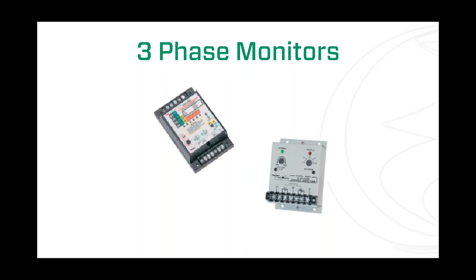So again, we start talking about 3-phase pumps, we start talking about expensive pumps typically, I would highly recommend considering one of these devices. Otherwise, you might find yourself being blamed for a burned up pump, and nobody might have even known that they'd lost a phase. But if you had one of these guys in your control panel, not only would you have known that you'd lost a phase, but you would have prevented burning up that expensive pump. So I can't say enough good things about these guys.